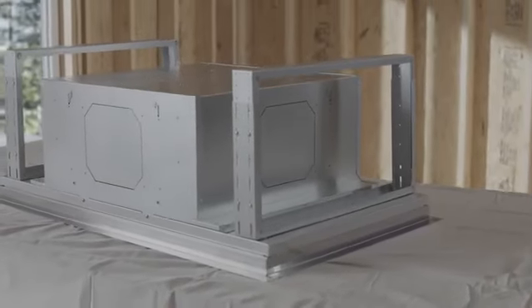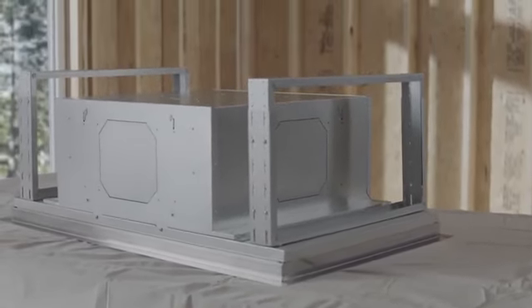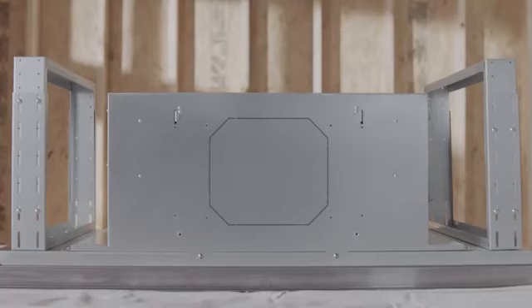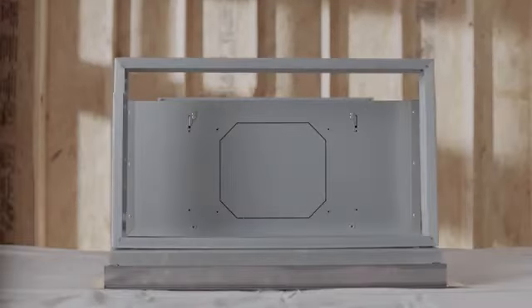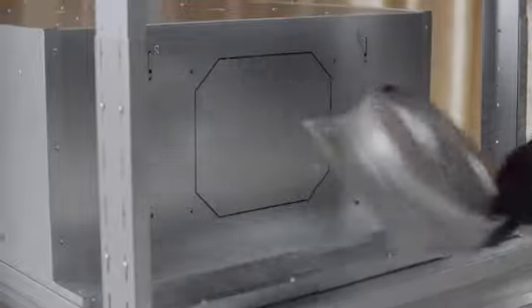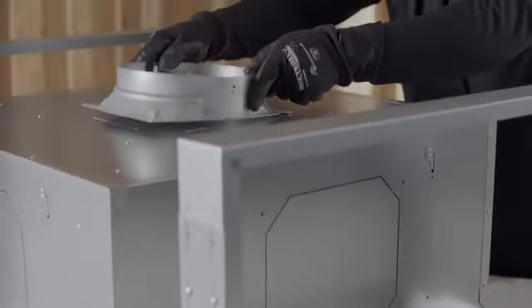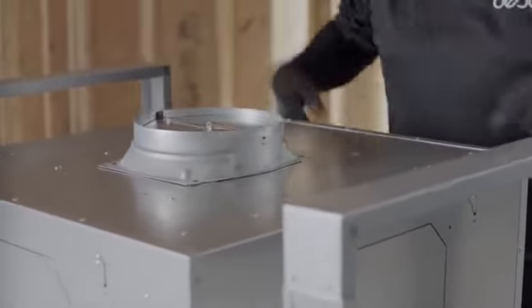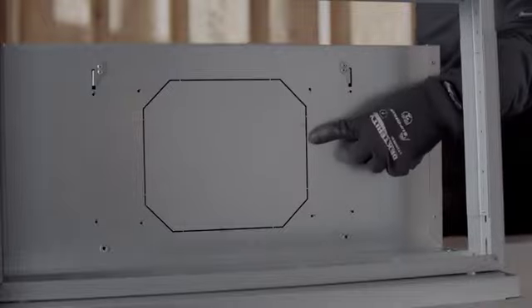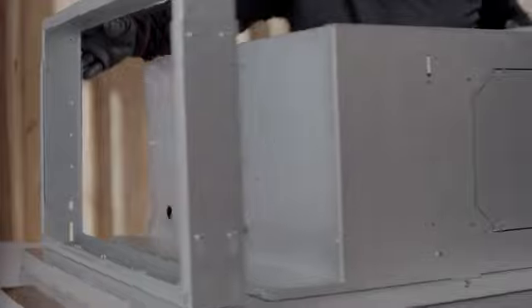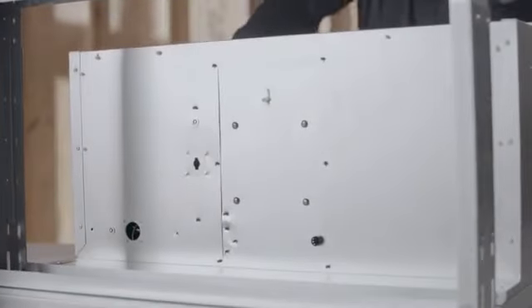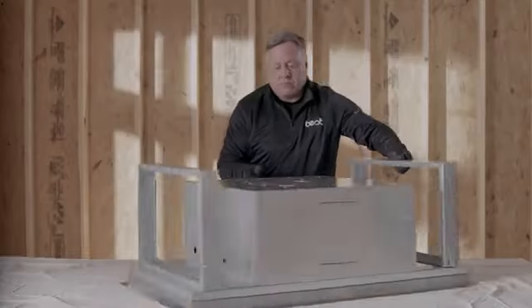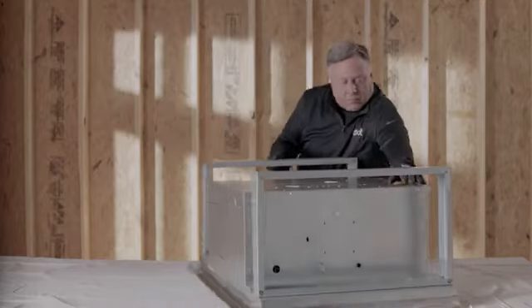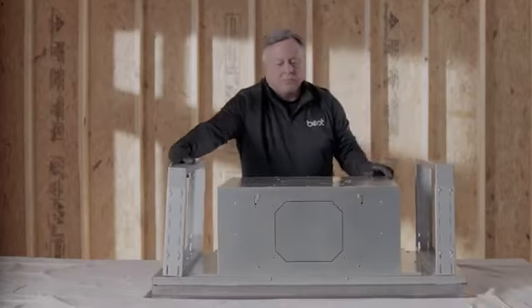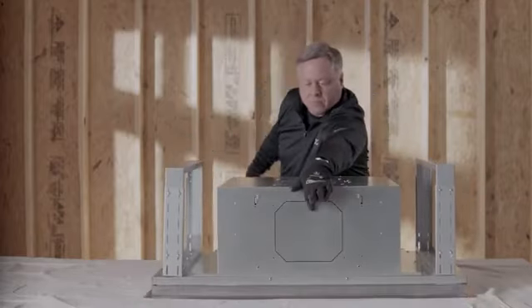Now, let's work through the 4 possible blower outlet positions: top, front, back, and side. When using the side or top outlets, you can install the damper prior to mounting into the ceiling. Note that there is only one exit for side exhaust. Orient the unit so the side outlet is facing the desired direction. In the case of front and back outlet positions, the damper must be installed on the housing once the hood is installed in the ceiling.